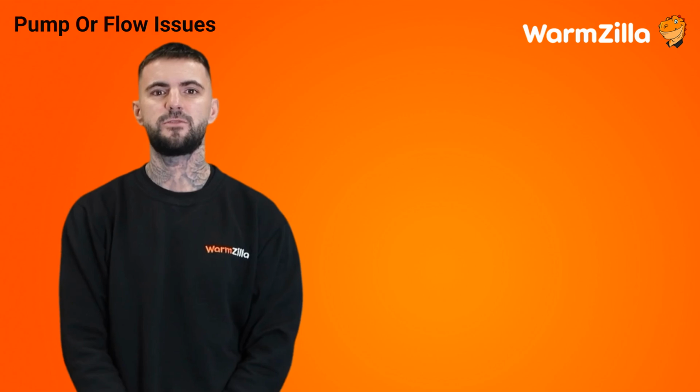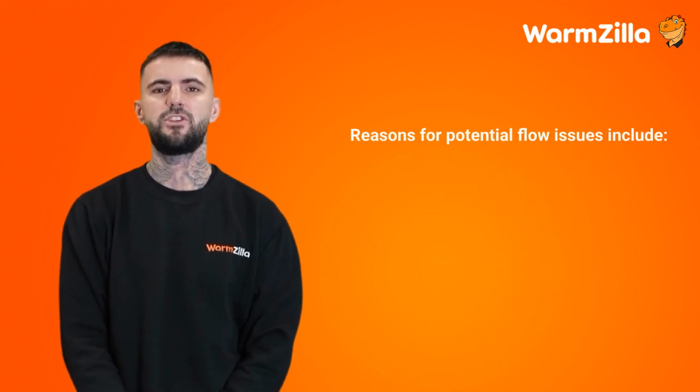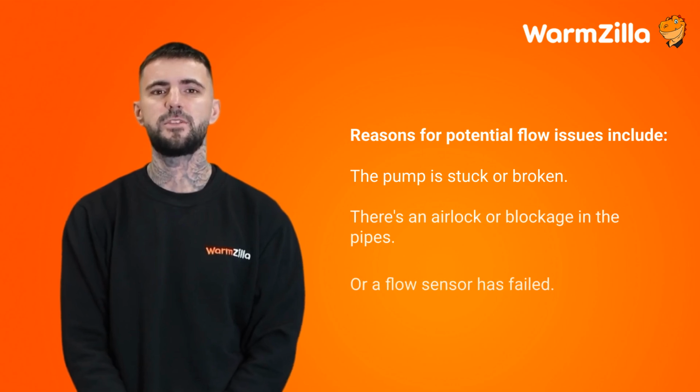Pump or flow issues. Your boiler's pump needs to circulate its water throughout your home. If an issue is left unaddressed for an extended period, your home's heating system may overheat or even break down. Reasons for potential flow issues include the pump is stuck or broken, there's an airlock or blockage in the pipes, or a flow sensor has failed.